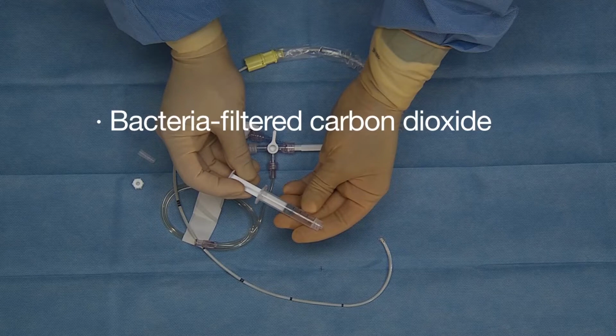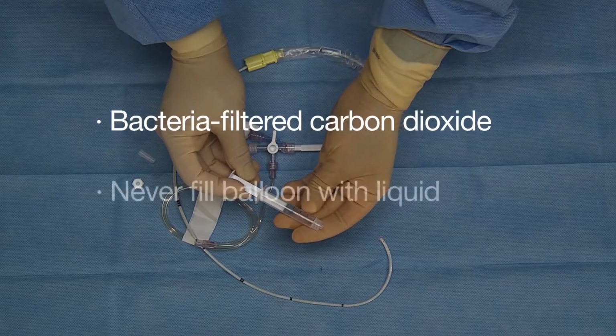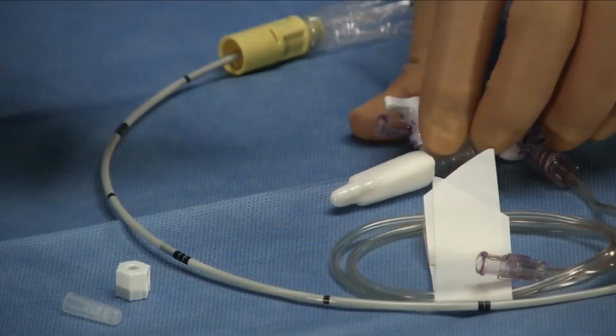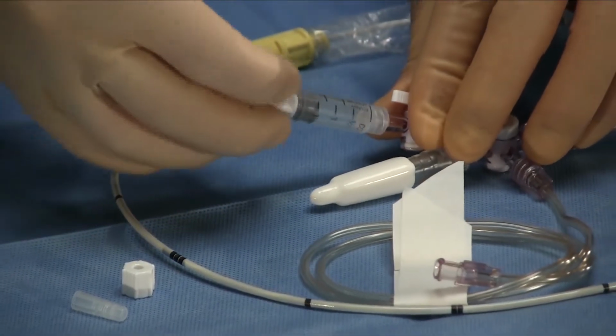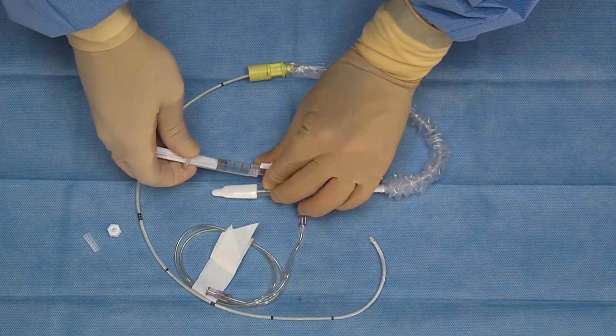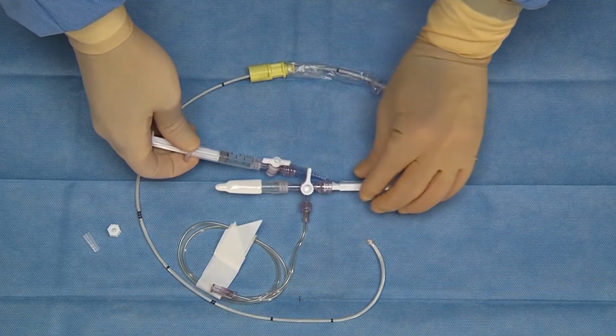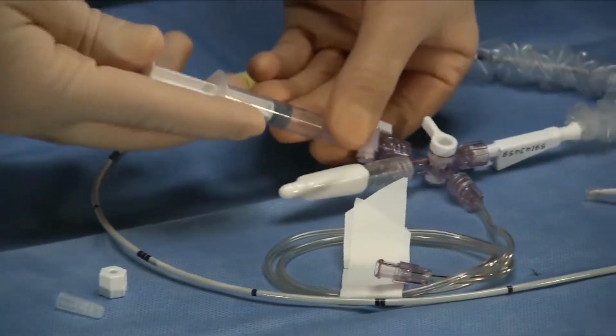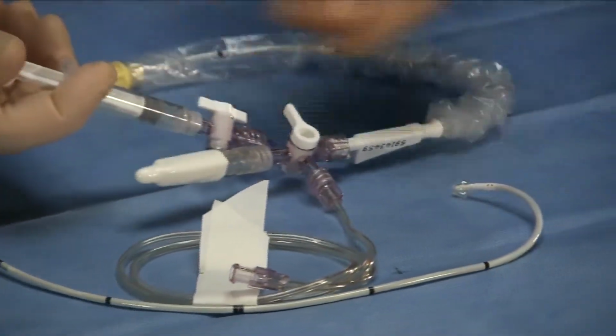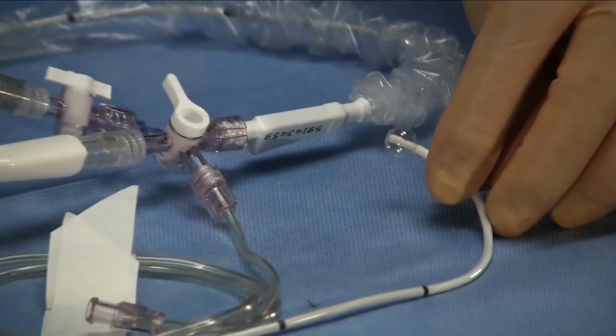It is important to remember that the EndoVent balloon is never inflated with liquid, as this is a flow-directed catheter that requires air or carbon dioxide in the balloon to function properly. Attach the filled syringe to the two-way stopcock. Verify that the two-way stopcock is open to the catheter. Depress the syringe plunger to fill the balloon with air. Verify the balloon's integrity.